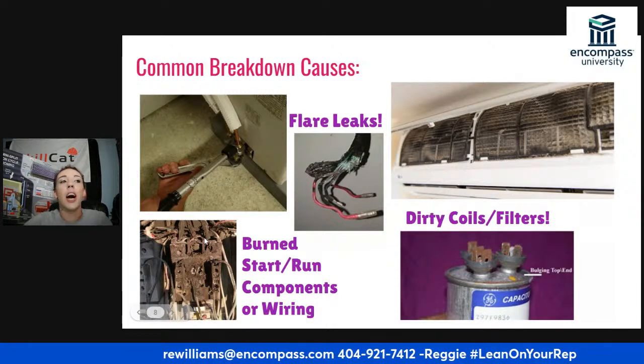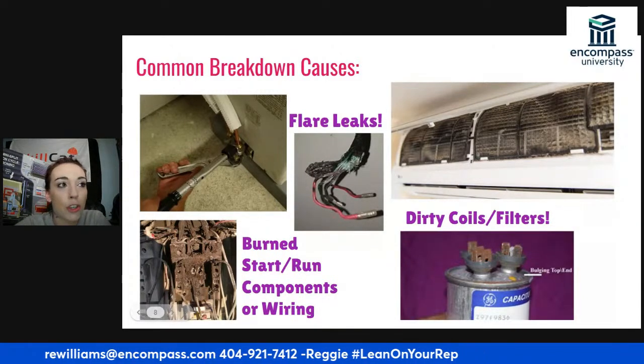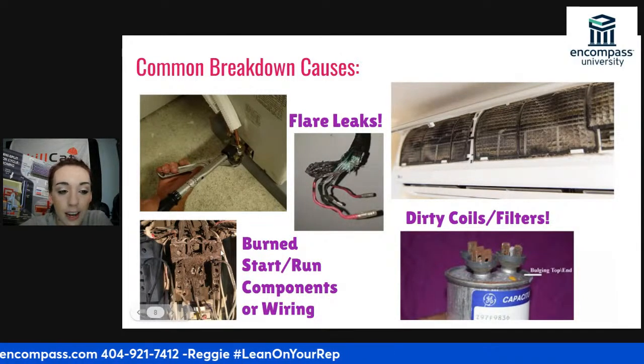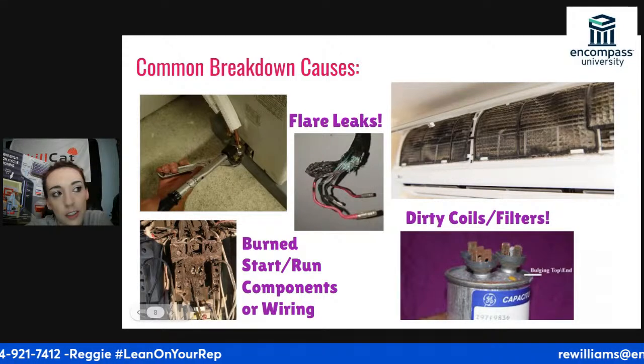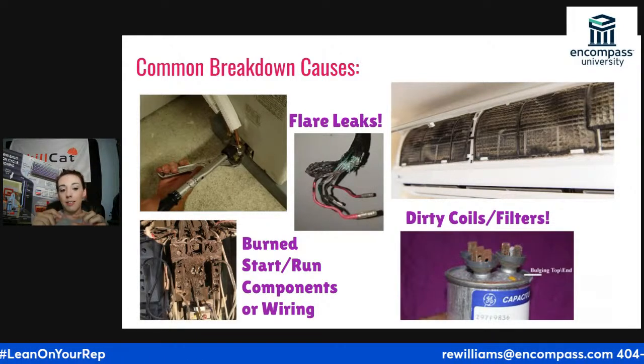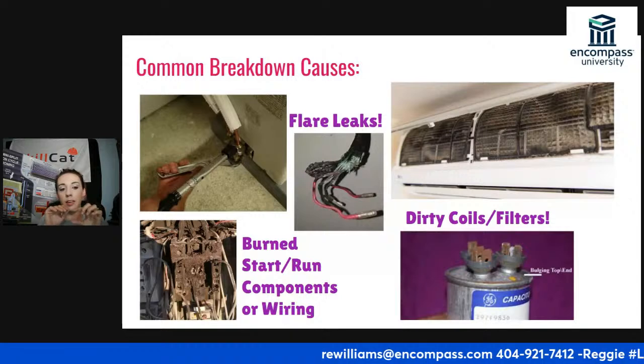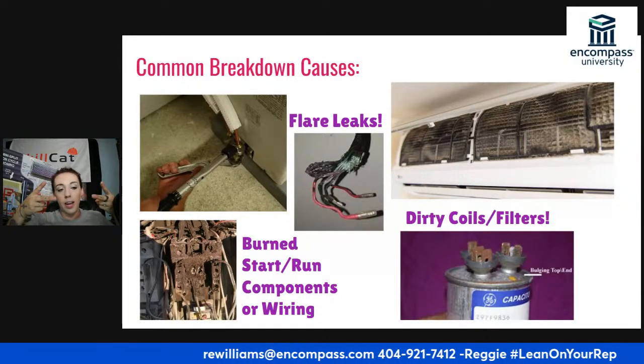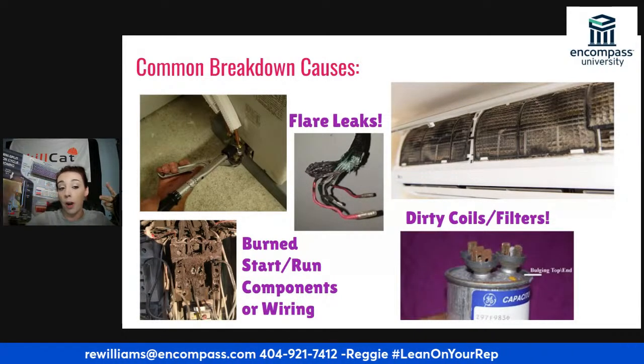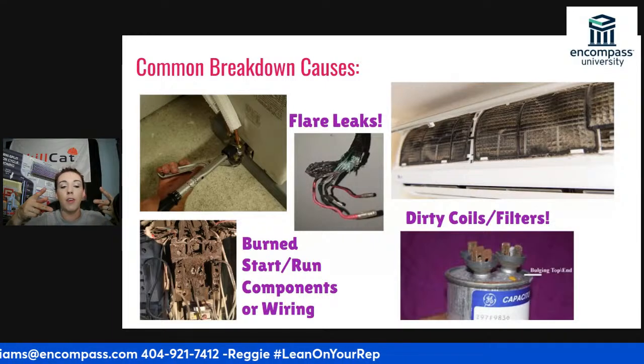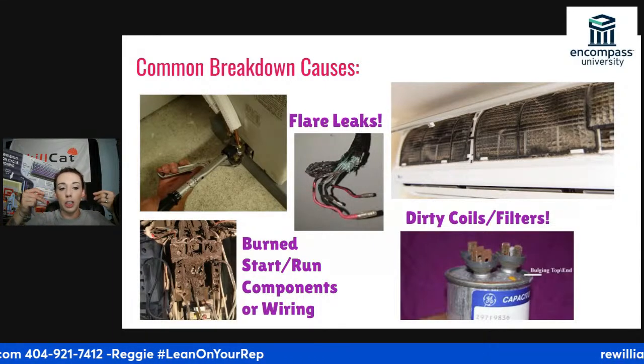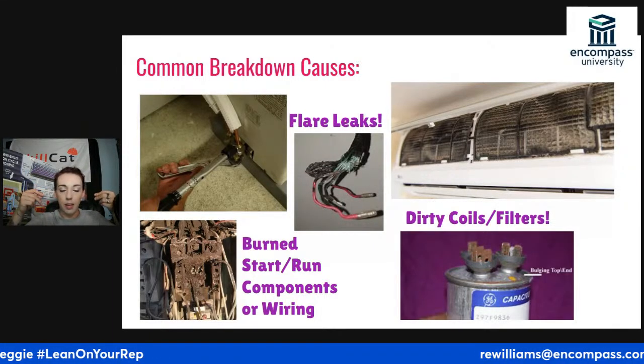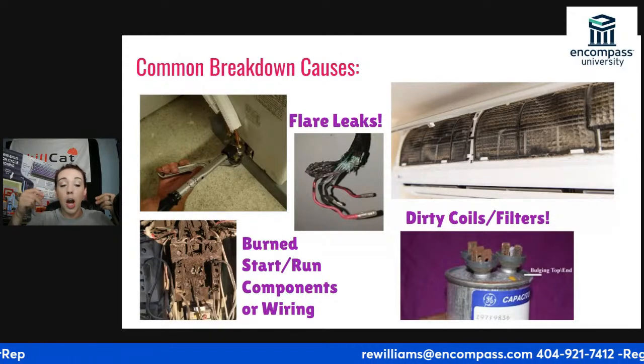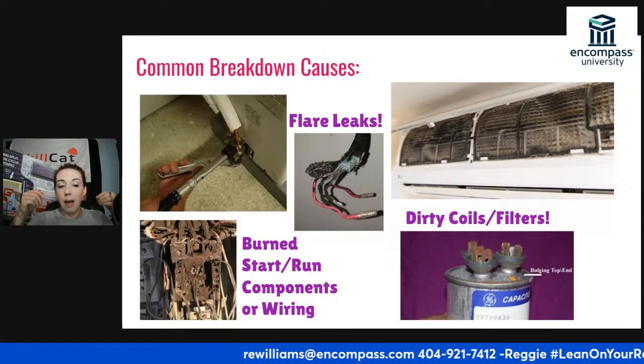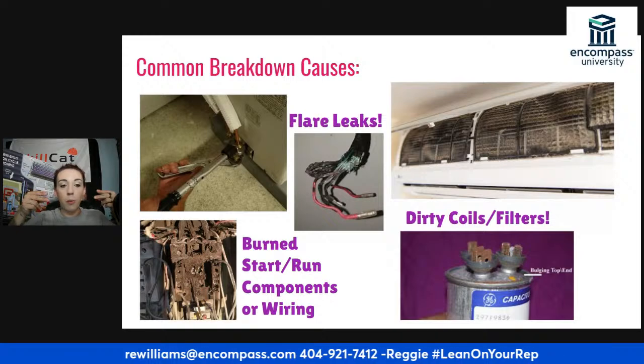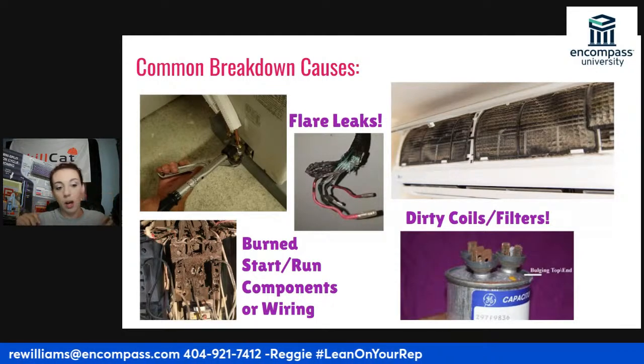So when we have a contactor that is burnt, usually it's on one contact or two contacts. For those of you who know about contactors, it has a mechanism that pulls in. And once that pulls in, the 4 contacts, L1, L2, T1, and T2, or there are more on bigger, industrial stuff, they will pull in and touch. So they touch the contacts behind them. So when those contacts are dirty, we can't make a good connection. So they will kind of chatter. We call it contactor chatter.